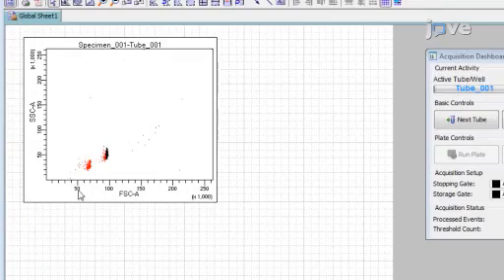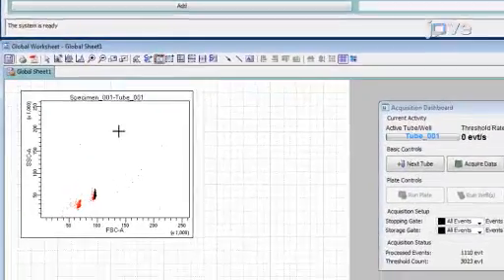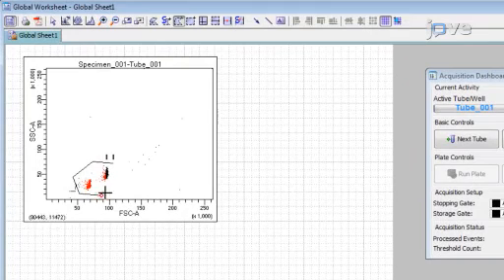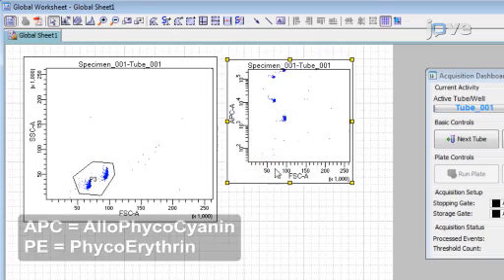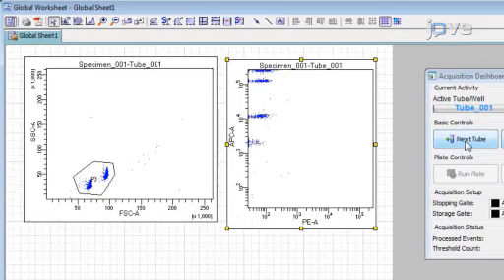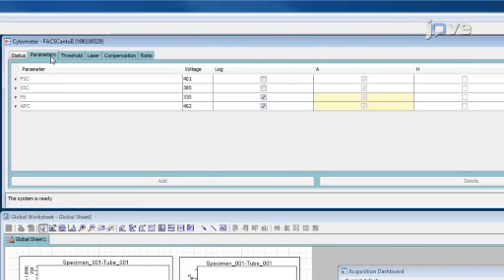Adjust the forward scatter threshold to exclude unwanted events. In the forward scatter versus side scatter plot, draw a gate that includes all bead populations. Display the gated bead populations from the forward scatter versus side scatter plot on the second dot plot with PE on the X axis and APC for the Y axis. Adjust the PMT voltage for the APC fluorescence channel so that the APC signal for all bead populations has a median fluorescence intensity or MFI that lies between 10 and 5,000.